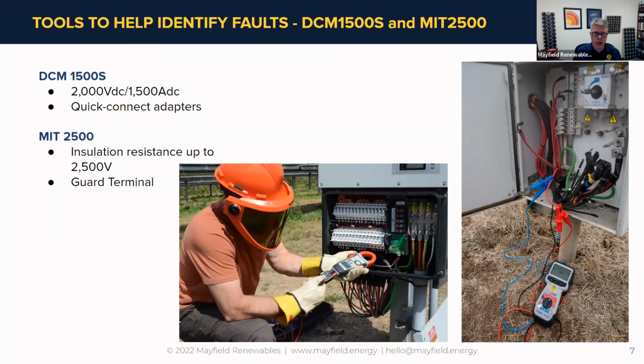Using insulation resistance testers, you can start to segment your array. You can start at a larger value and look at the conductors on the output of a combiner box, for example. If you have a central inverter, you can isolate different components and segment out the different sections of the array, starting big and then going smaller and smaller to help identify where the ground faults are. That's one of the things we really talk about on the troubleshooting side, segmenting out the array like that. But Mike, what did I miss on the MIT?